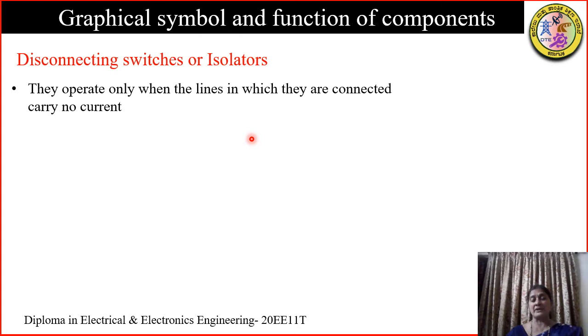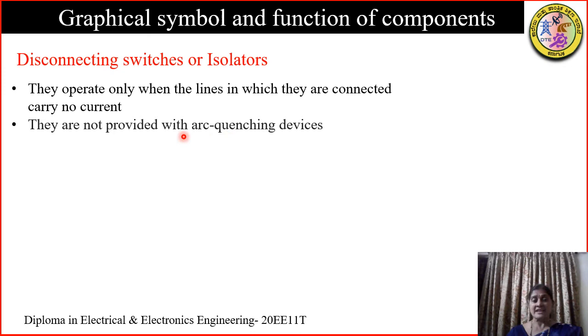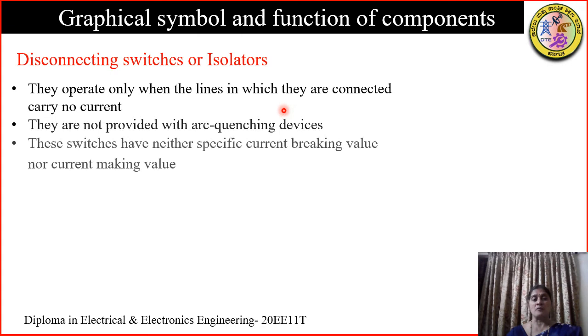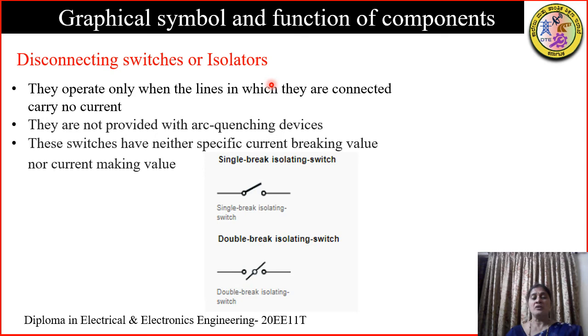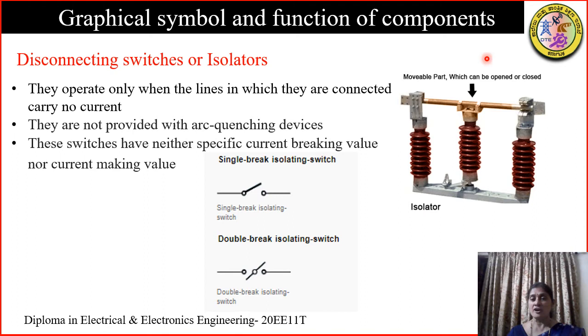Unlike the circuit breaker, which operates when load current is flowing, isolators will operate when there is no load current. So the isolator is not an arc quenching medium and has no making or breaking value. In the figure, we can see graphical symbols of different types of isolating switches — either a single break or a double break isolator. This is how an isolator looks; the movable part can be opened and all three contacts operate together.